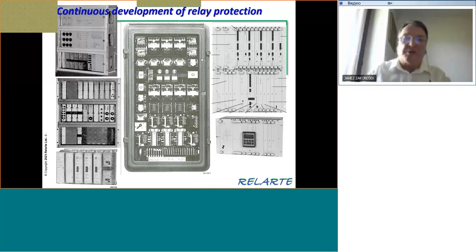So just a little bit more, when we come to static relays, here is one busbar protection, which was produced by ASEA in Sweden, introduced in 1970, with operating time between 5 to 10 milliseconds, and with minimum time to CT saturation, which is maybe very important still today, of 2 milliseconds. It means that if the CT saturated after 2 milliseconds, this protection always operated very reliably.